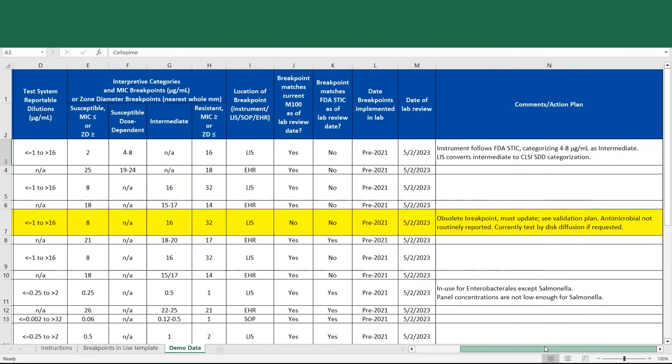The date of the most recent lab review is listed. And then there's a column for comments and an action plan. So in this case, it's noted that the instrument follows the FDA STIC categorizing isolates with MICs of 4 to 8 as intermediate. But as the laboratory is chosen to follow CLSI breakpoints, their laboratory information system converts these values from being reported as intermediate to instead report them as susceptible dose dependent.